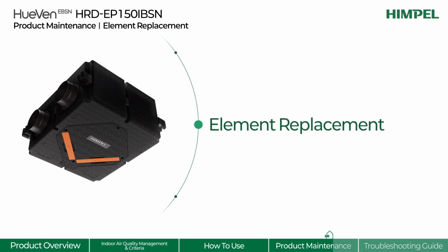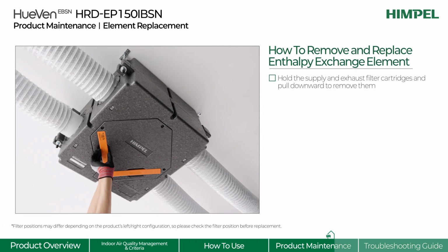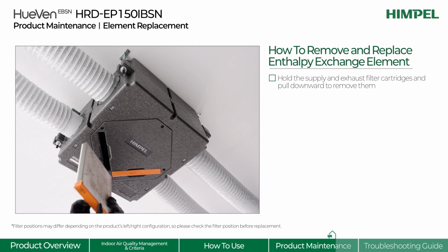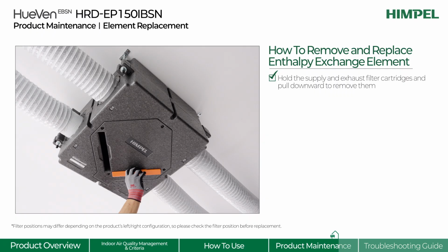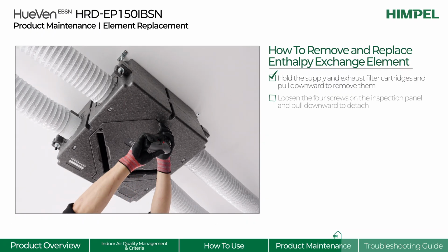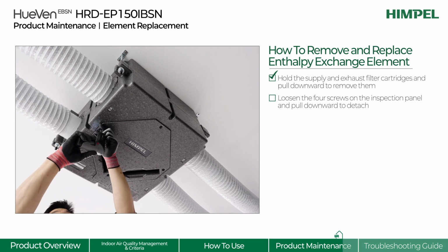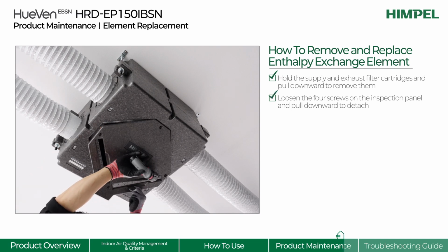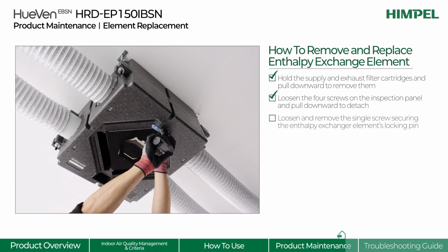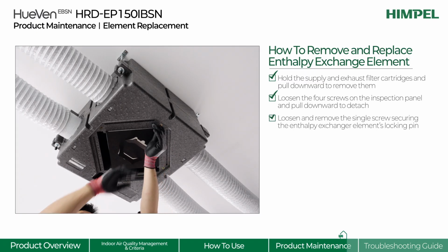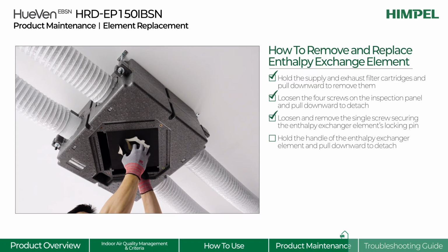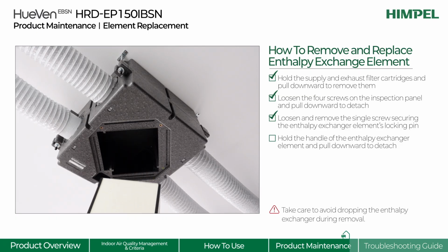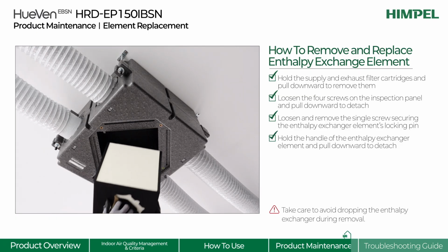Element replacement. Please hold the supply and exhaust filter cartridges and pull downward to remove them. Loosen the 4 screws on the inspection panel and pull downward to remove it. Loosen and remove the single screw securing the element's locking pin. Hold the handle of the enthalpy exchanger element and pull downward to remove it.